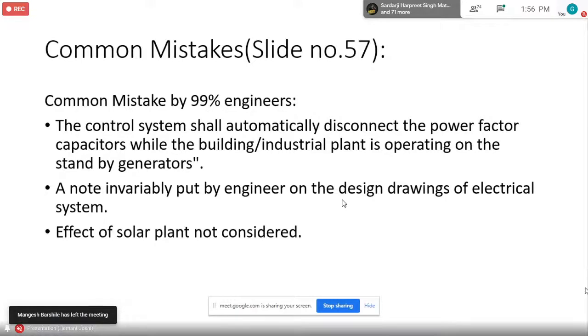So if you are having a solar plant, then what happens is that it is set at unity power factor, to keep the inverter size down. So it means the grid has to supply the rest of the power, which will lower your power factor. So if you are having a solar power plant, you will need a bigger size capacitor bank than the normal one.